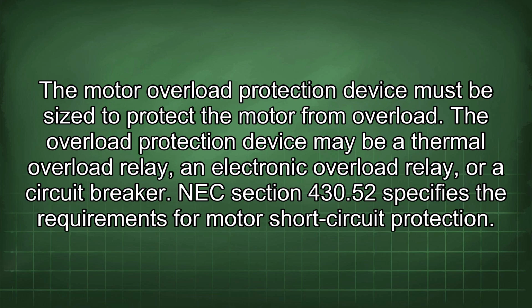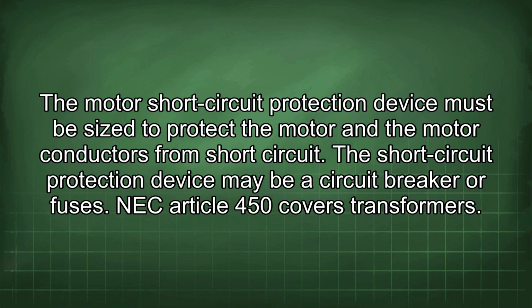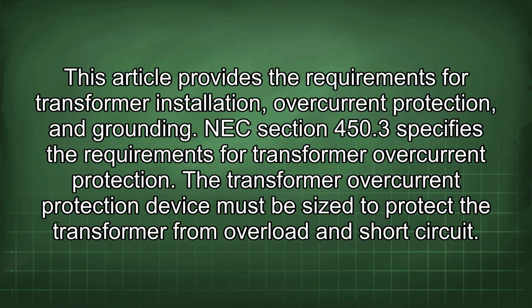NEC Section 430.52 specifies the requirements for motor short circuit protection. The motor short circuit protection device must be sized to protect the motor and the motor conductors from short circuit. The short circuit protection device may be a circuit breaker or fuses. NEC Article 450 covers transformers. This article provides the requirements for transformer installation, overcurrent protection, and grounding. NEC Section 450.3 specifies the requirements for transformer overcurrent protection.